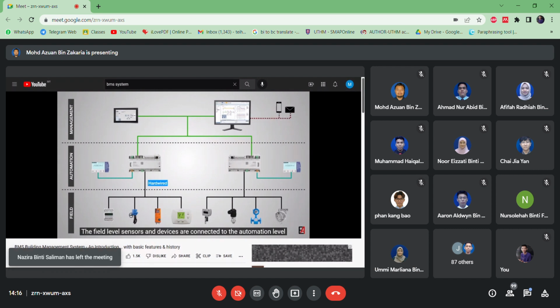The field level sensors and devices are connected to the automation level via hardwired connections, typically with a single pair of cables. The operator terminal can be connected either via a bus cable or a standard Ethernet cable. The automation level is connected to the management level via BACnet IP protocol using building structural cabling methods.